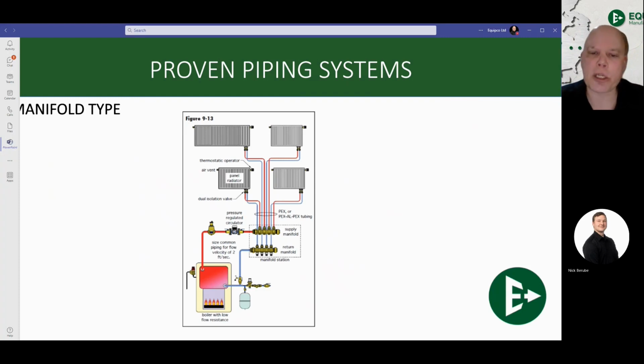Now, one last piece that I just want to show off, this is with regard to what a manifold distribution type is like. Most folks use manifolds only for radiant in-floor. Just so you know, there are a ton of applications you can use manifolds for, such as a home run system for radiators. It's an extremely fast and effective way to pipe in radiators inside of a home. Personally, I'm a huge fan of rads. Radiant, take it or leave it. Radiators, yes please, fill your boots.